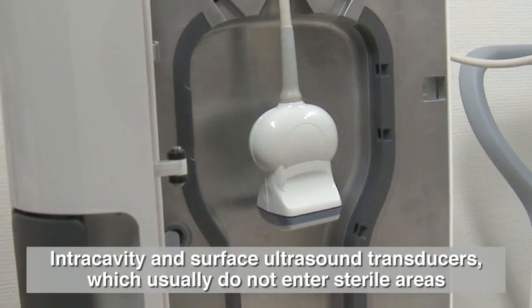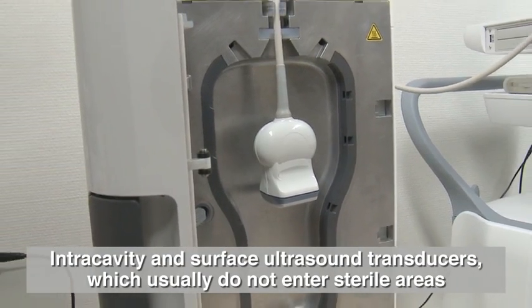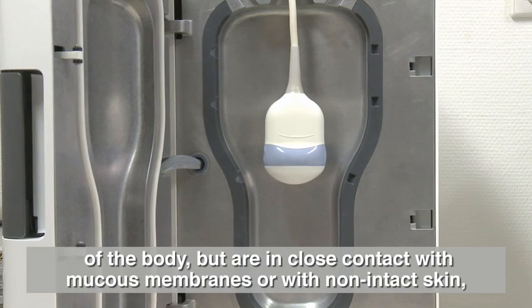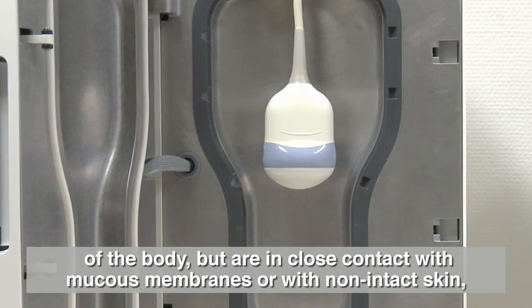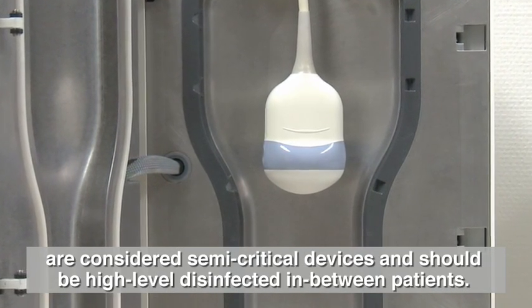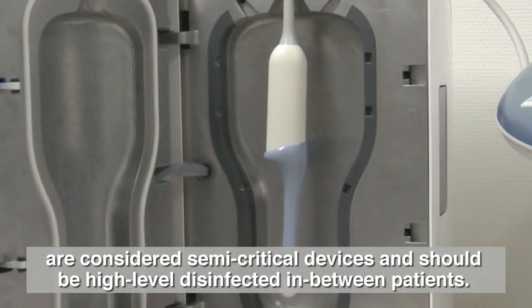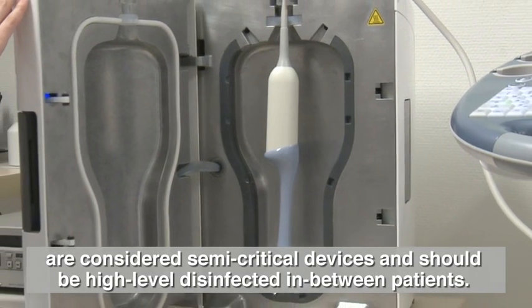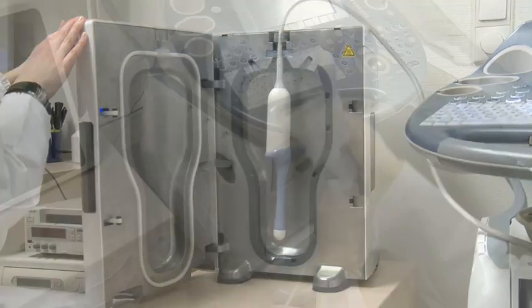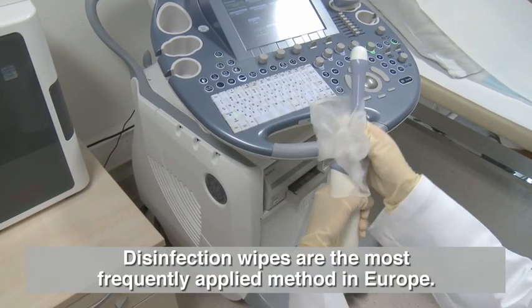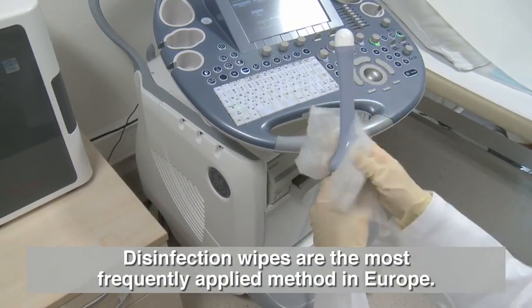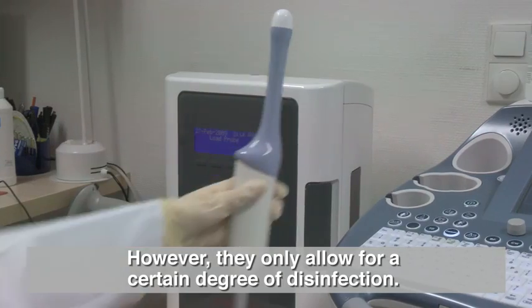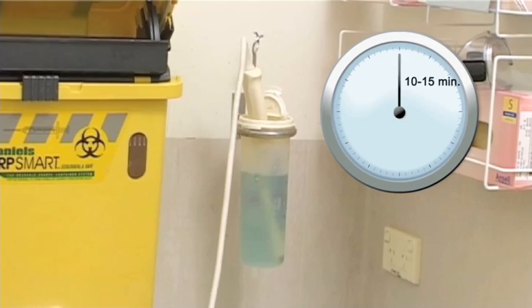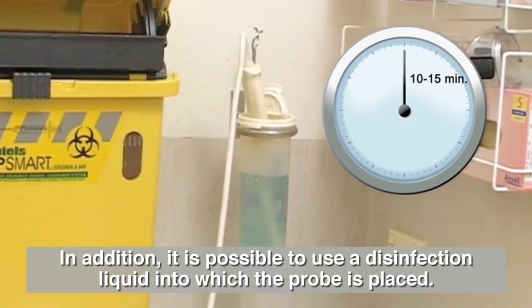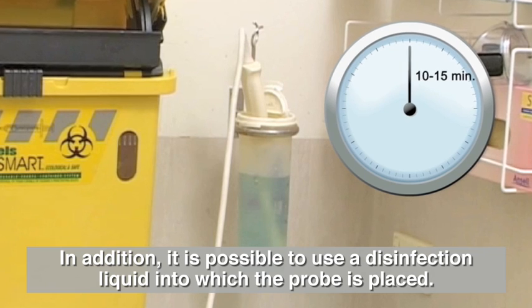Intracavity and surface ultrasound transducers, which usually do not enter sterile areas of the body but are in close contact with mucous membranes or with non-intact skin, are considered semi-critical devices and should be high-level disinfected in between patients. Disinfection wipes are the most frequently applied method in Europe. However, they only allow for a certain degree of disinfection. In addition, it is possible to use a disinfection liquid into which the probe is placed.